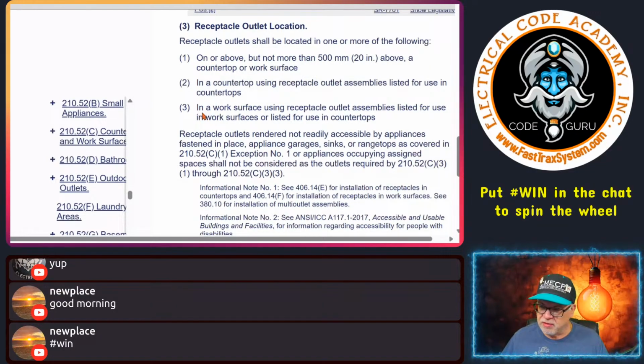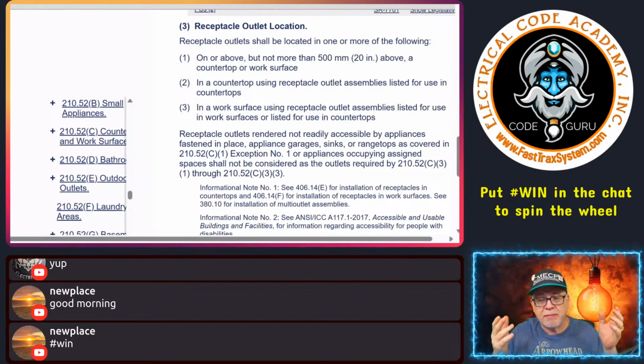And then, of course, the third allowance is in work surfaces using receptacle outlet assemblies listed for use in the work surfaces or listed for use in the countertop. So if you get a countertop or a work surface in a kitchen and the receptacles are literally built into it as part of the work surface, and they're listed for use in that countertop, meaning it comes that way, then that's not a problem either. They're fine. You can leave them. But again, they're not going to be below anything. They're usually built into the face or the top, or pop up or flip up. Again, no face-up receptacles, but if it comes in the equipment or comes that way, it's okay.